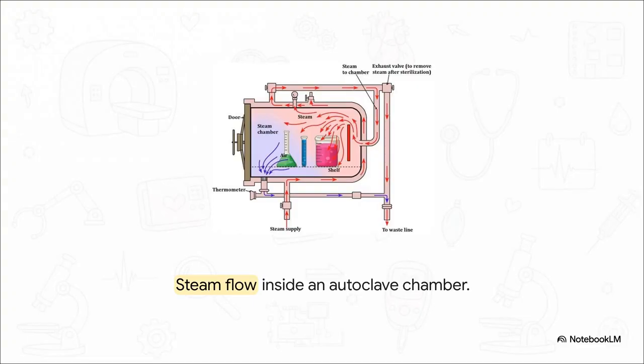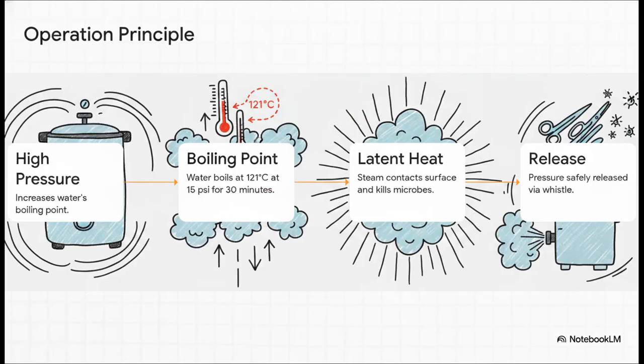What's actually happening inside one of these things is pretty wild. The hot steam blasts into the chamber, and because of how it's designed, it forcefully displaces the cooler air, pushing it down and right out through the bottom. This super precise circulation pattern is exactly what guarantees that every single instrument inside reaches the critical temperature necessary for total 100% sterilization. And this is where the physics gets absolutely fascinating.